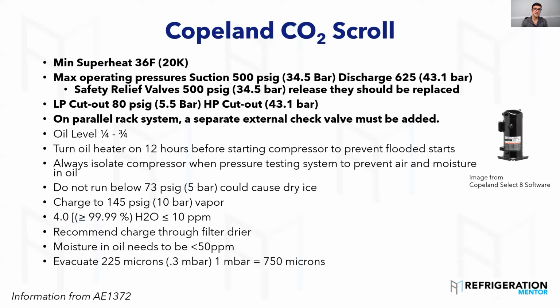Another thing, and I've seen this many times doing a field audit going out with contractors, is that certain compressors need to have check valves added on a parallel rack system. What I mean by parallel rack system is multiple compressors tied in with a discharge and a suction line, a header. On rack systems, a separate external check valve must be used. Inside the discharge there is a spring-loaded check valve, but it's not for this purpose, and it's not to 100% stop everything. It's really to stop it from rotating backwards.